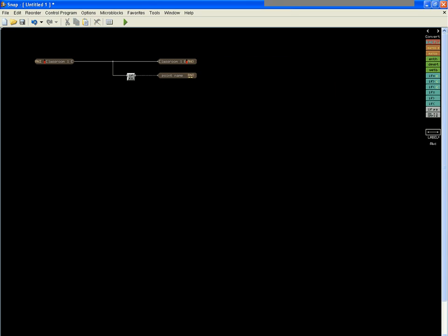So now I'm taking the CO2 from one system and sending it out to the other CO2. So I can pass the CO2 between two VAV boxes, or if I wanted to, I can pass it to another one, or if I wanted to do a completely different CO2 sensor, I can select all of this, copy this, and paste it. So you can do multiple VAV boxes in one equipment file and not have to create an equipment file per VAV box.